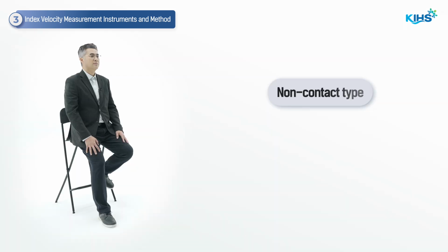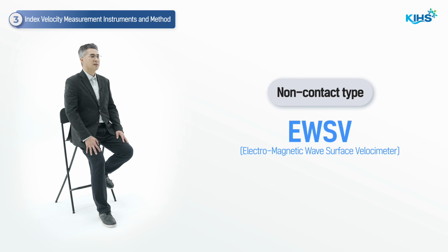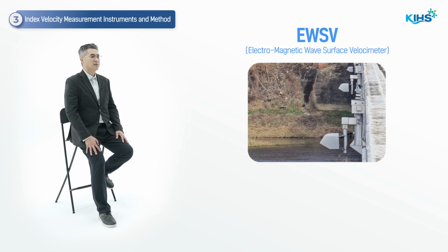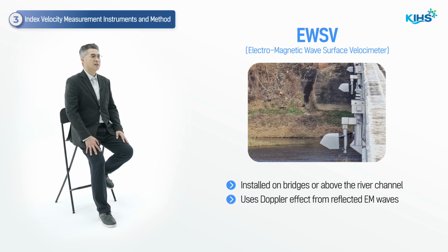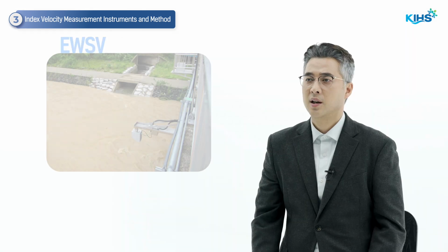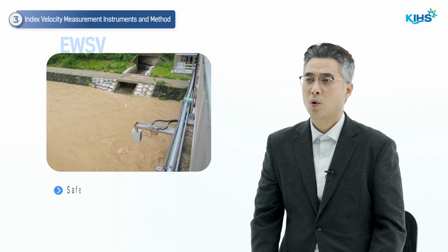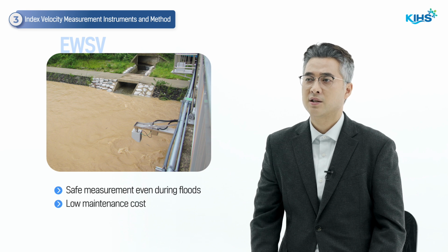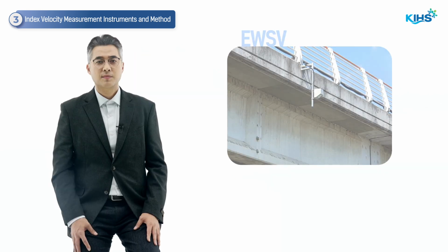Next, let us look at the non-contact instrument, the electromagnetic wave surface velocimeter, or EWSV. This instrument is installed on bridges or above the river channel and measures surface velocity via the Doppler effect, using electromagnetic signals reflected from the water surface. Because it is non-contact, measurements remain safe even during floods, and maintenance costs are relatively low.